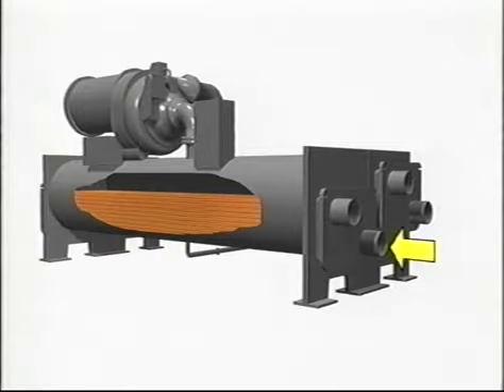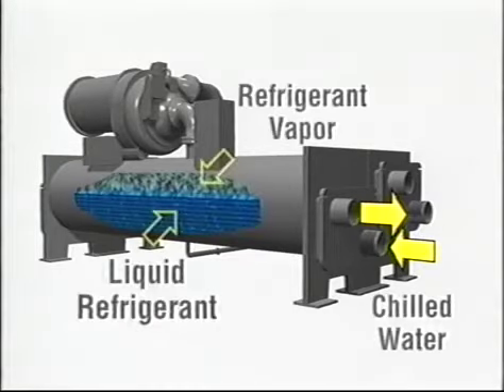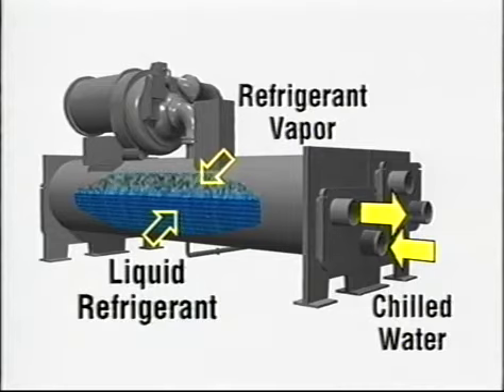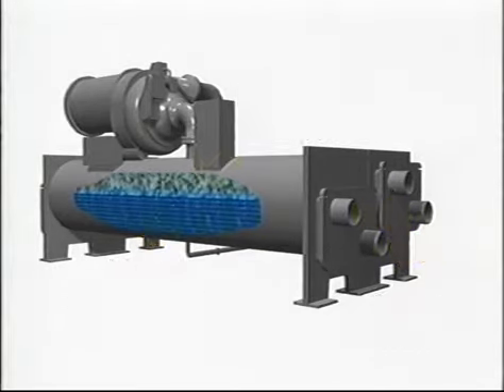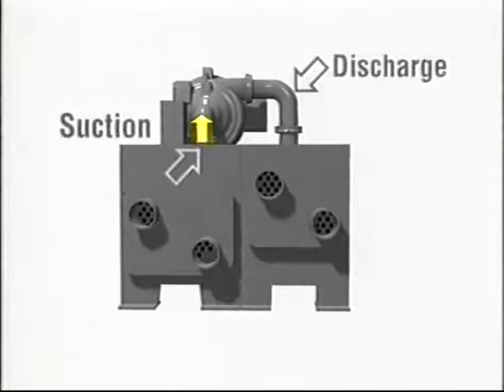The chilled water that circulates through your building runs through the tubes, giving up the heat it gained in the building to the HFC 134A refrigerant that is outside the tubes. When the cooled water leaves the cooler, it's ready to recirculate to the building and absorb more heat. The refrigerant outside the tubes in the cooler is in liquid form, and as it absorbs heat from the water in the tubes, some of it vaporizes and flows upward into the compressor. The compressor acts as a pump, causing the refrigerant to circulate through the chiller. In it, the vapor is compressed and leaves the compressor at a higher temperature and pressure.